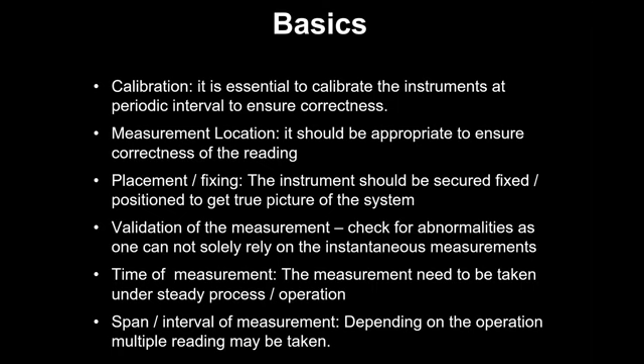Here again, I'll share one example. We were doing an audit for a very large company, and they had a huge cooling water system. The pumping load was literally in megawatts, and they had a huge pipeline, almost 1 meter diameter, a common header, through which we needed to measure the flow. After a certain distance, maybe 2-3 meters, the pipeline was underground till the condenser, and at the condenser it was rising.